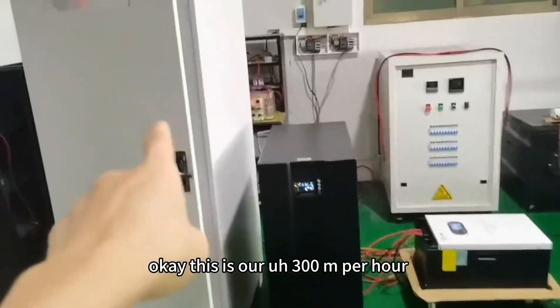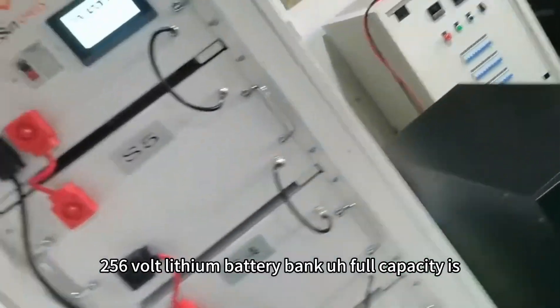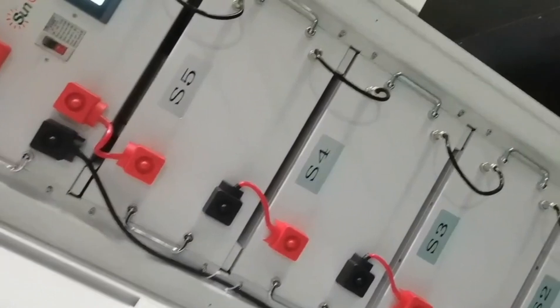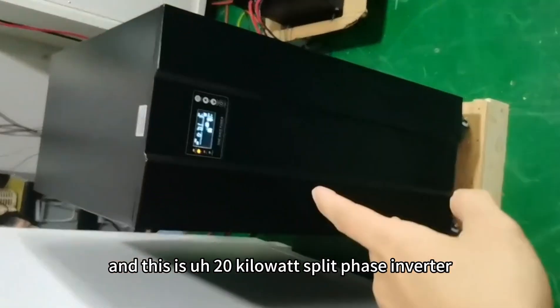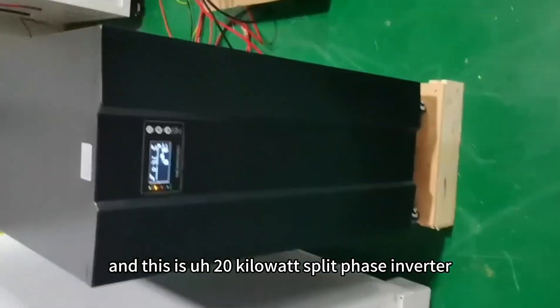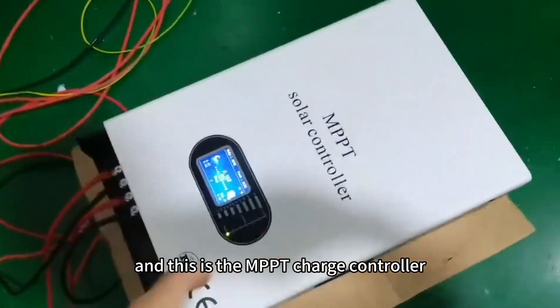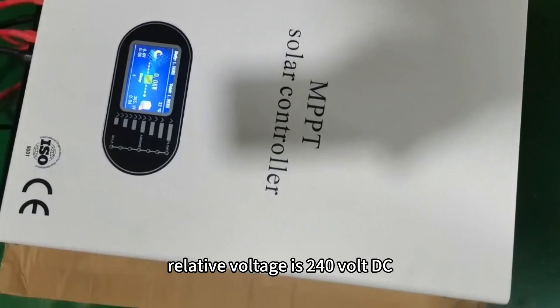This is our 300 ampere-hour 256 volt lithium battery bank. Full capacity is 76.8 kilowatt-hours. This is a 20 kilowatt split phase inverter, and this is the MPPT charge controller — 100 ampere, rated voltage 240 volt DC.